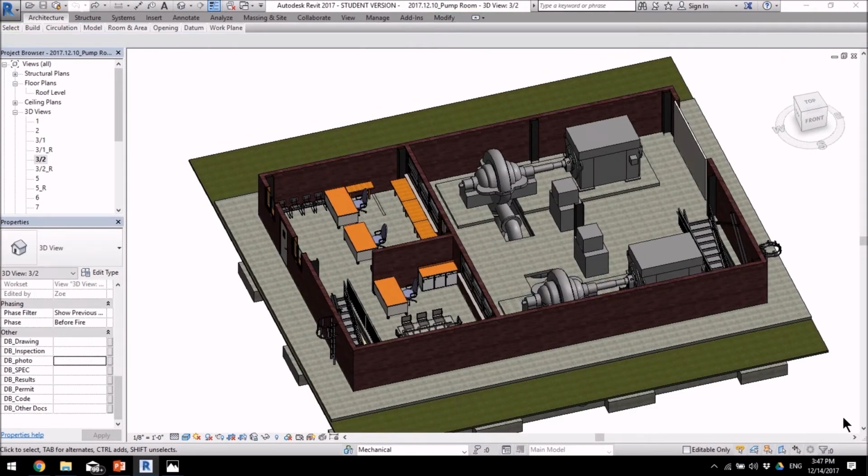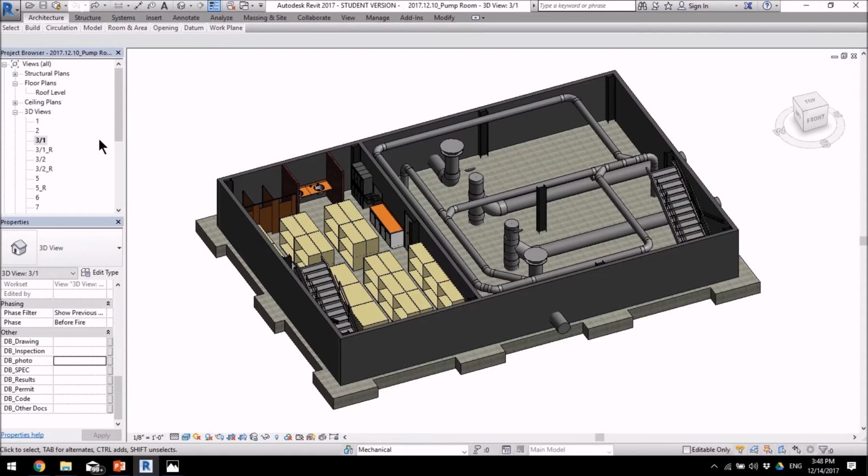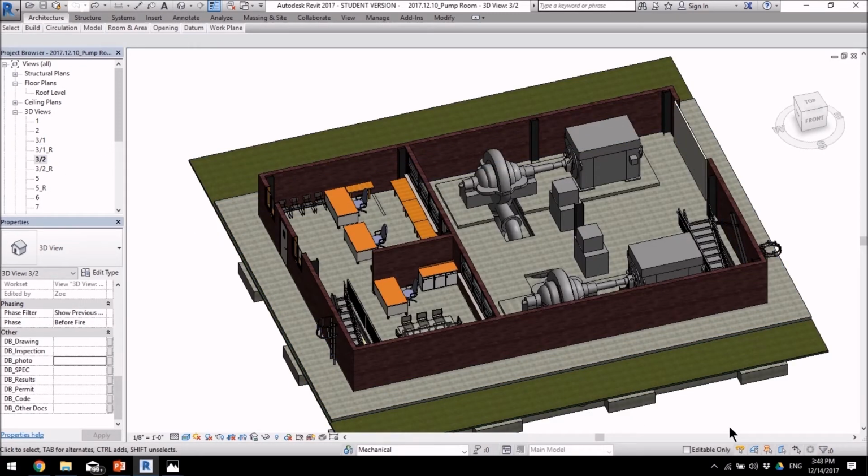By running a post-incident structural analysis using the finite element analysis software, we are now capable of having a deeper understanding of the succession of events and the cause and effect relationship of the fire in regards to the damages inside of the pump station building. Specifically, by running the software, we can see the failure mechanism and the causal relationship between the fire inside the storage room and the damages to the equipment in the other parts of the building.